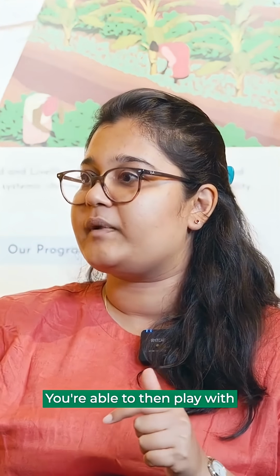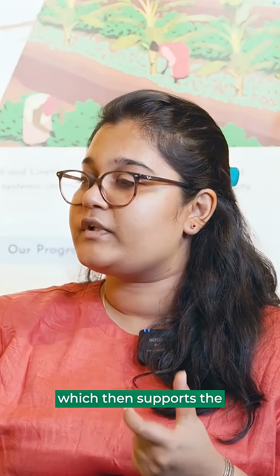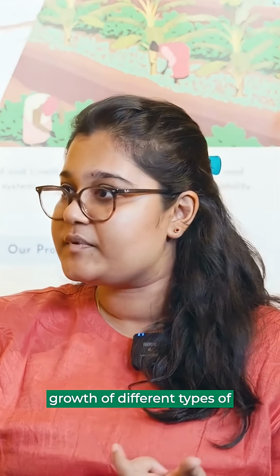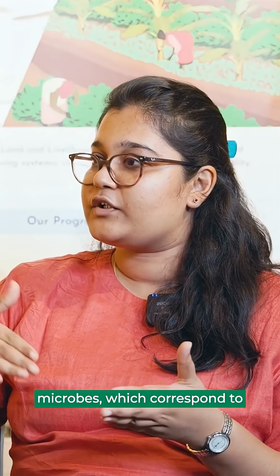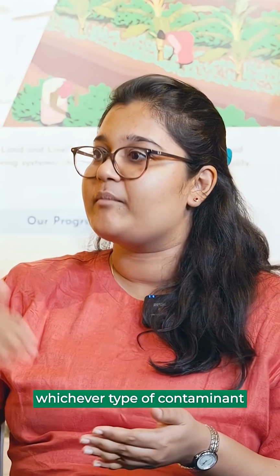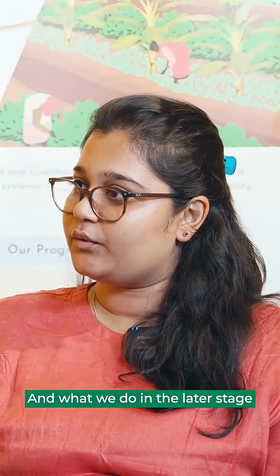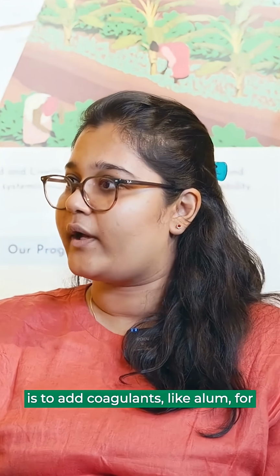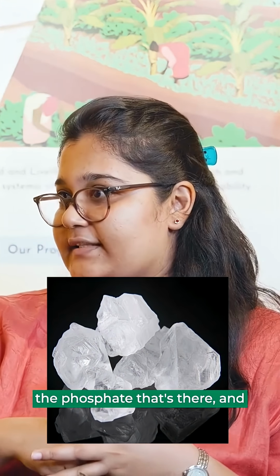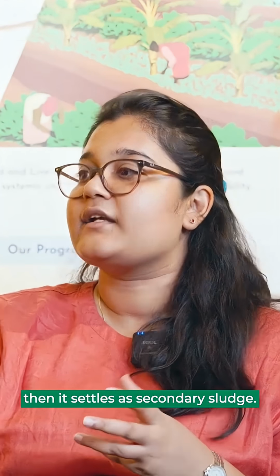So you're able to then play with different levels of oxygen, which then supports the growth of different types of microbes, which correspond to whichever type of contaminant you're looking to remove. And what we do in the later stage is to add coagulants like alum, for example, which is great to bind with the phosphate that's there, and then it settles as secondary sludge.